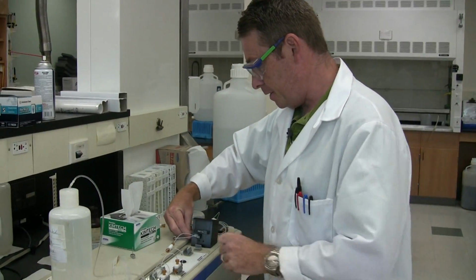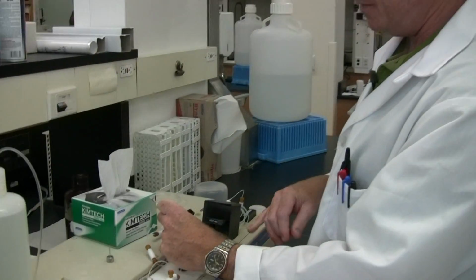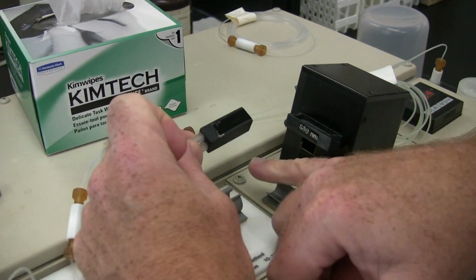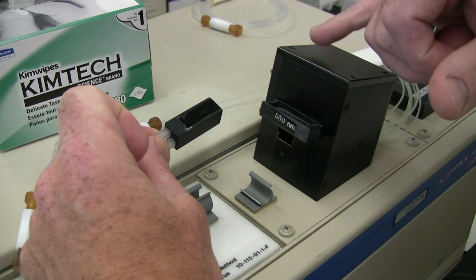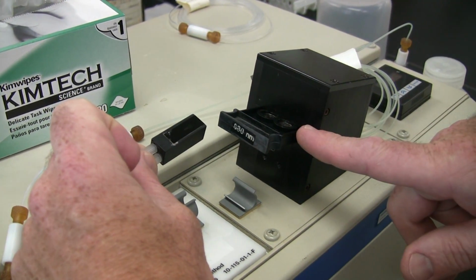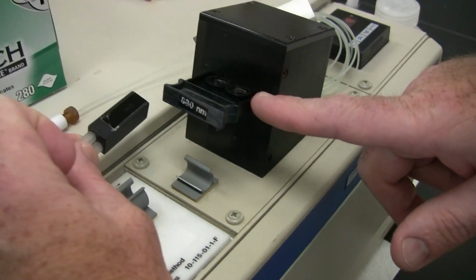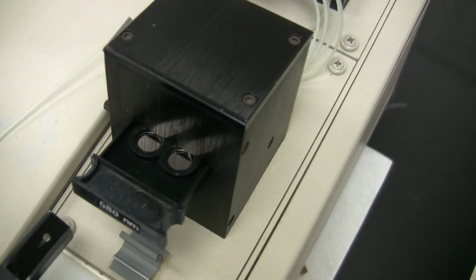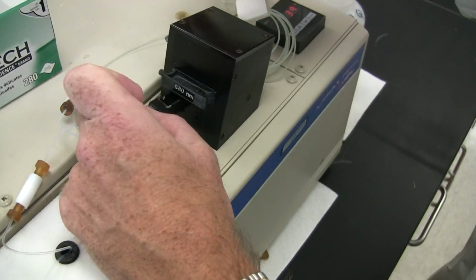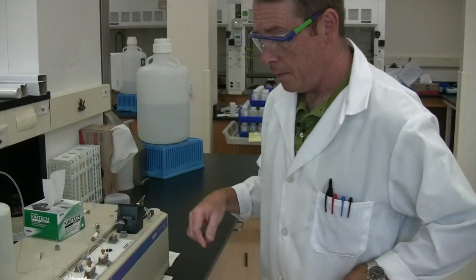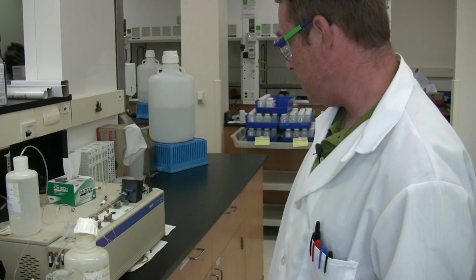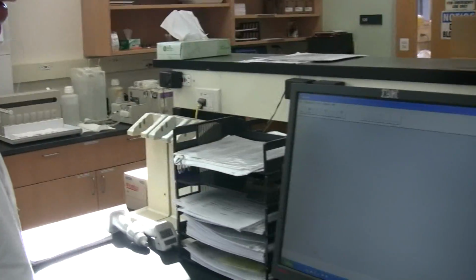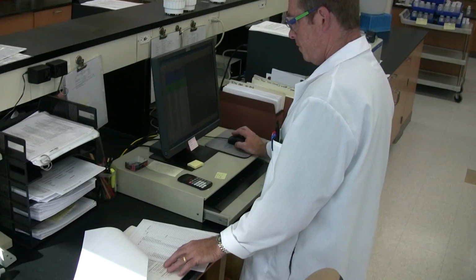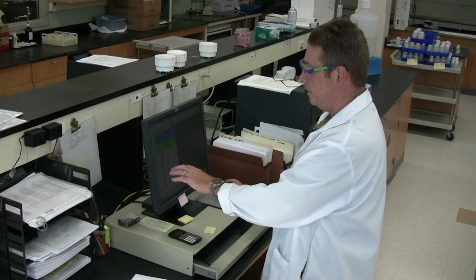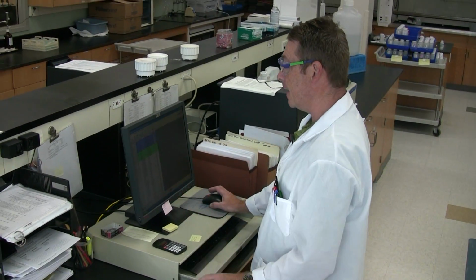Two things I didn't show you here is, once the color does develop, it goes through a flow cell and light shines through from the bottom, and a detector will detect the absorbance, and this is a filter at 880 nanometers. That is the wavelength where the blue color is most sensitive for the absorbance. So now we have our reagents going. One thing I do have to do is define the run in the instrument in the software itself. So basically this tells the instrument what samples it's going to be running and where they are in the racks.